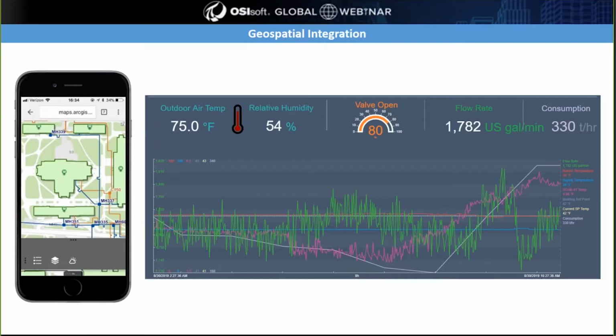Continuing with the example on this slide, we know there's a correlation between chilled water consumption, temperature, and humidity. So we build analytics within PI to model these relationships. Once we build the models, we can compare current consumption against our model prediction and create an alert if there's non-standard consumption. Right now on this screen, there's an outdoor air temperature of 75 degrees, relative humidity is 54%, and chilled water consumption is 330 tons per hour.